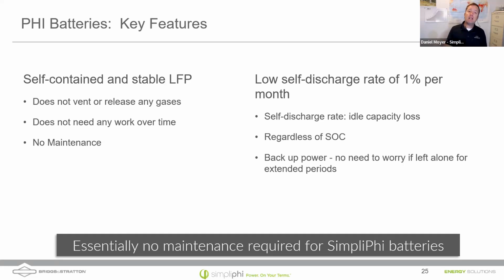So when you come back in summer or spring and it's time to recommission the system, the batteries will have enough juice in them to get the charge controllers to come alive, get the inverters to come alive, and of course make sure you get a good full bulk charge on those batteries before you start turning the loads on the next day.